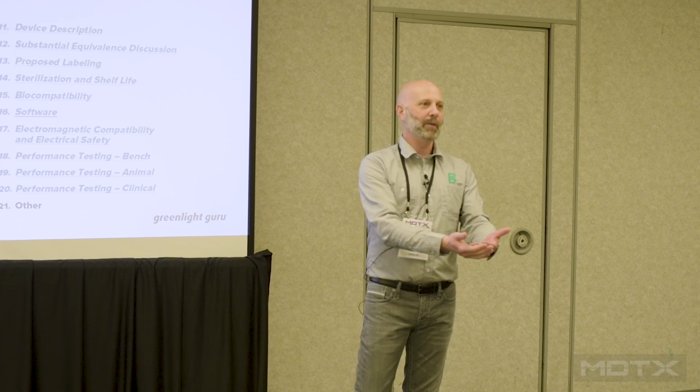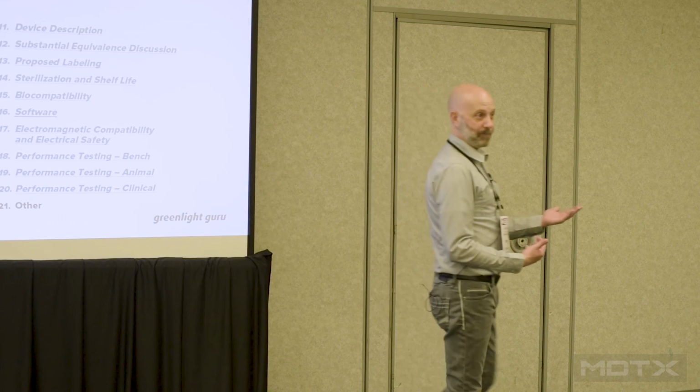Electromagnetic compatibility, it can be 12 weeks, it can be longer testing. It's a long type of test sometimes, and it can be very trying and very challenging. I may think that I got it, and then I go to the formal test, and I zap the only prototype that I have. Right? So some of these are all long lead time, very expensive, very time consuming. I may have everything else ready except for one or two of these items. So I used to be allowed to write an I promise statement. I could say, yeah, we have this started, we promise to complete this testing before we go to market. And FDA used to allow that.